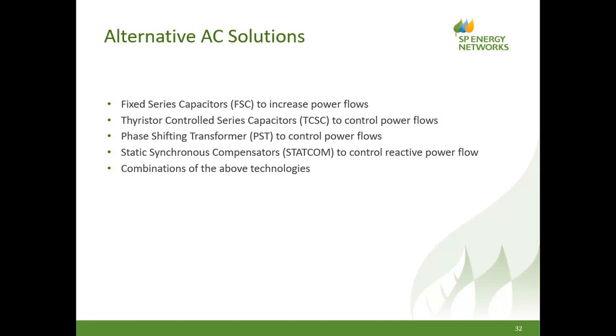If we wanted to control that power flow, we could put a thyristor controller on the series capacitor. So a thyristor controlled series capacitor is a competing technology to a DC link. Essentially, you can control the power flow, increase the power flow using thyristor controllers. We could have installed a phase shifting transformer to control power flows. So this would change the phase angle between the island and the mainland grids, thus allowing us to more precisely control the power flow.